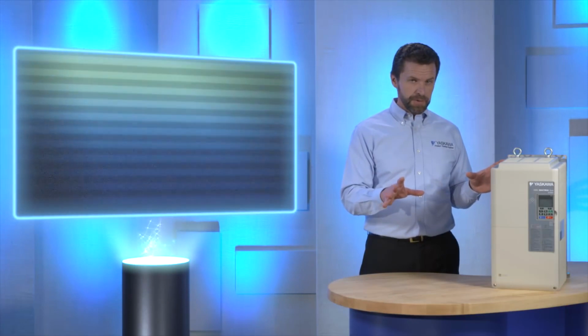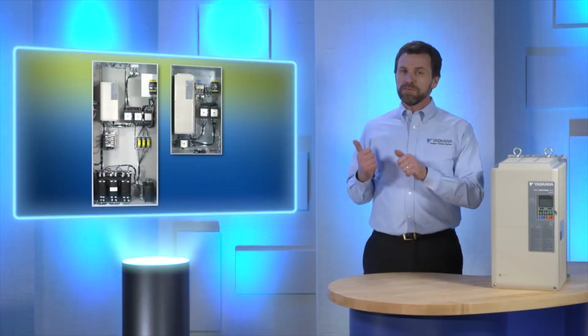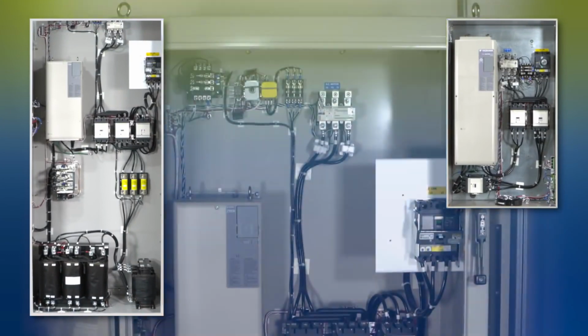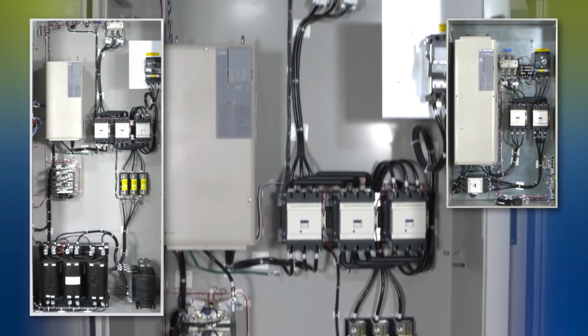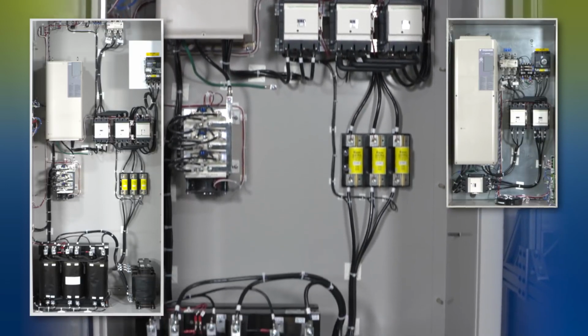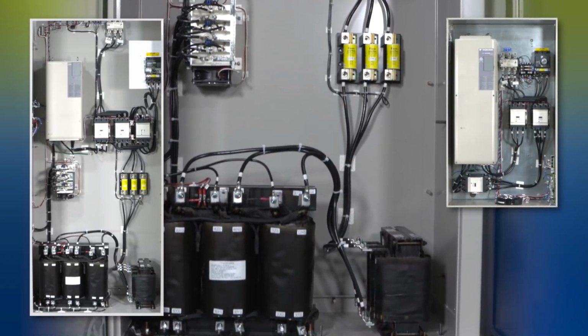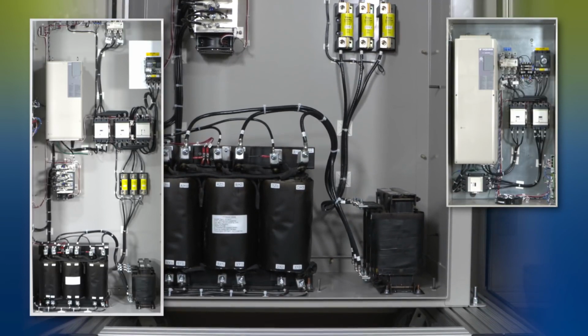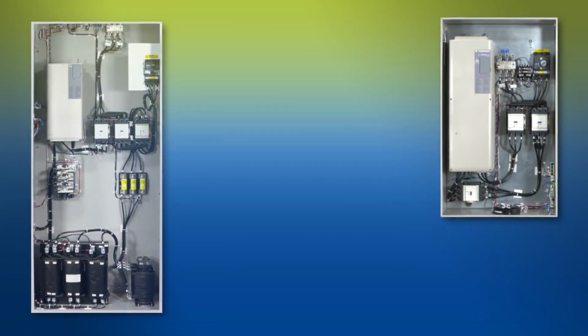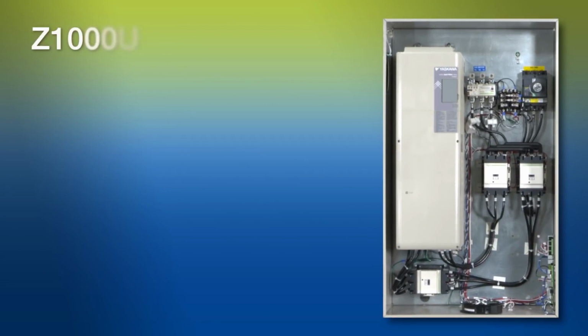Let's talk about some of the physical features of the drive. The all-in-one package of the Z1000U eliminates the need for external reactors and filters. Now, to give you a better idea of the smaller package size and low harmonic advantages of the Z1000U, here's a comparison showing a previous configuration, which includes external harmonic countermeasure components such as an external regenerative drive, input AC reactors, harmonic filter reactors, and capacitors. These components are not necessary with the Z1000U.